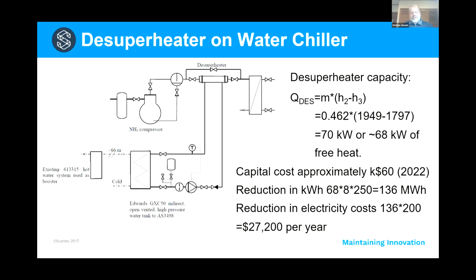The other rectangle to the right in the picture, that is the water-cooled condenser. And then you see down the bottom here, we have another heat exchanger, and that heat exchanger sits between the water we actually consume, the water that comes out of the taps, and the closed water circuit that we circulate between that heat exchanger and the desuperheater. We are required to have a double heat exchange for domestic hot water services, but we also need to have that water-to-water heat exchanger that you can see there.